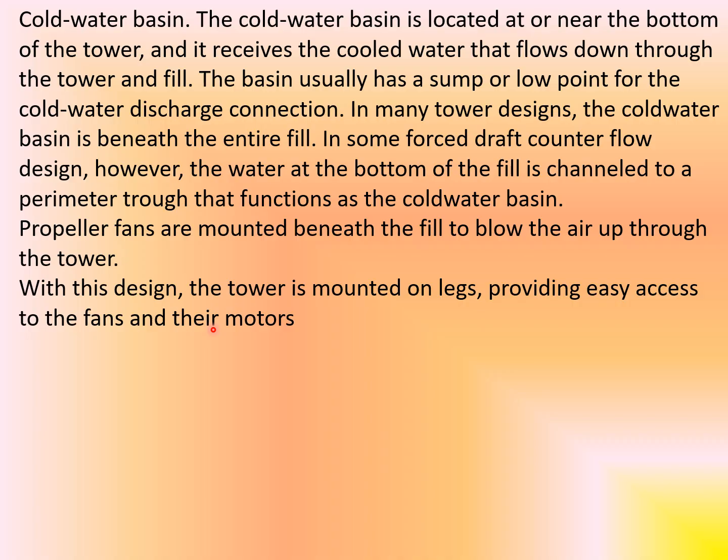Friends, now something about cold water basin. The cold water basin is located at or near the bottom of the tower and it receives cool water that flows through tower and fill. The basin usually has a sump or low point for cold water discharge connection. In many tower designs, the cold water basin is beneath the entire fill.